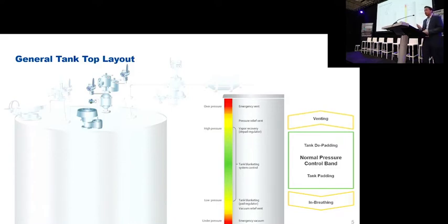Over here, we have an example with a flame arrestor underneath. Let's say you have a very highly flammable gas or flammable gas in your tank. Breather valves will always leak. You are always leaking a little bit of the process gas to atmosphere. If you were to have a spark or a lightning flash or something, you can generate a flame or an explosion which could propagate into your tank. A flame arrestor is there to stop that from happening, to protect your tank.